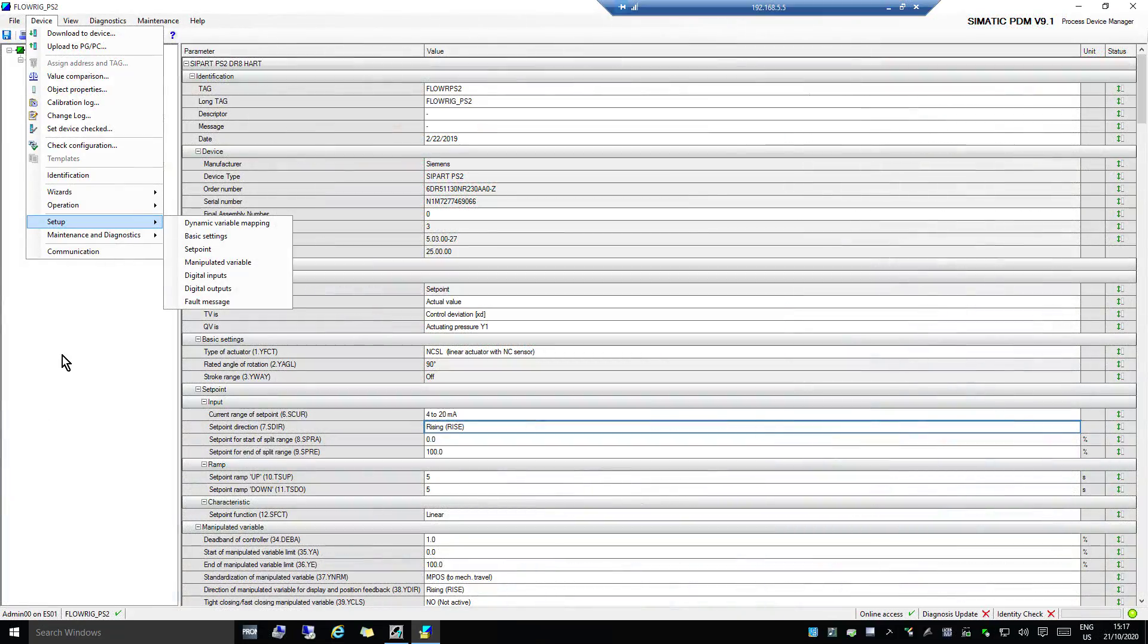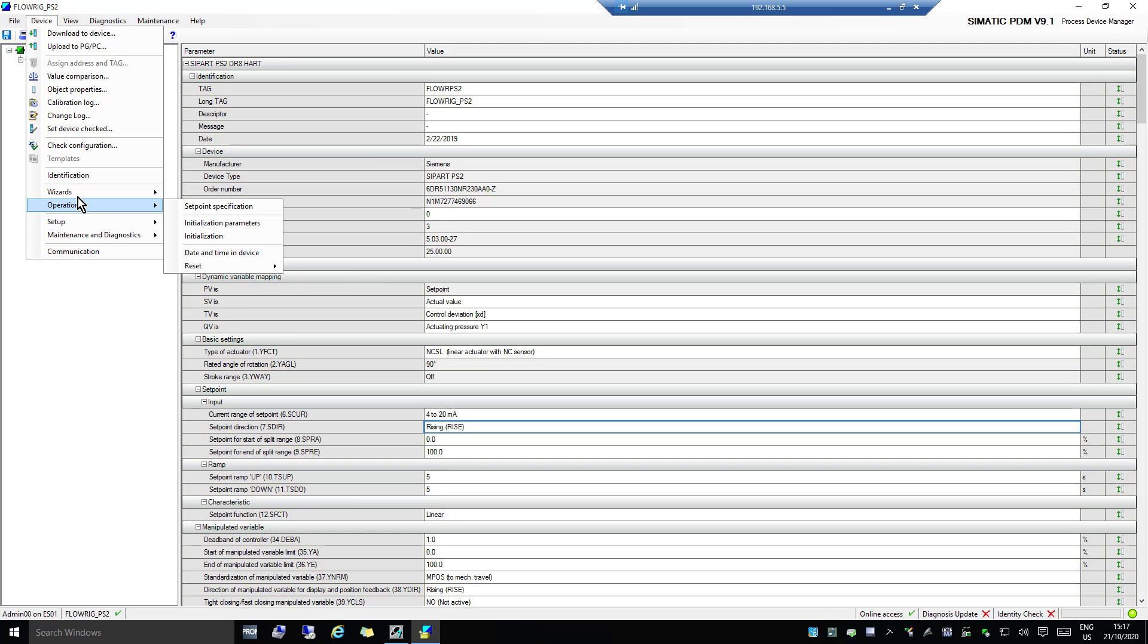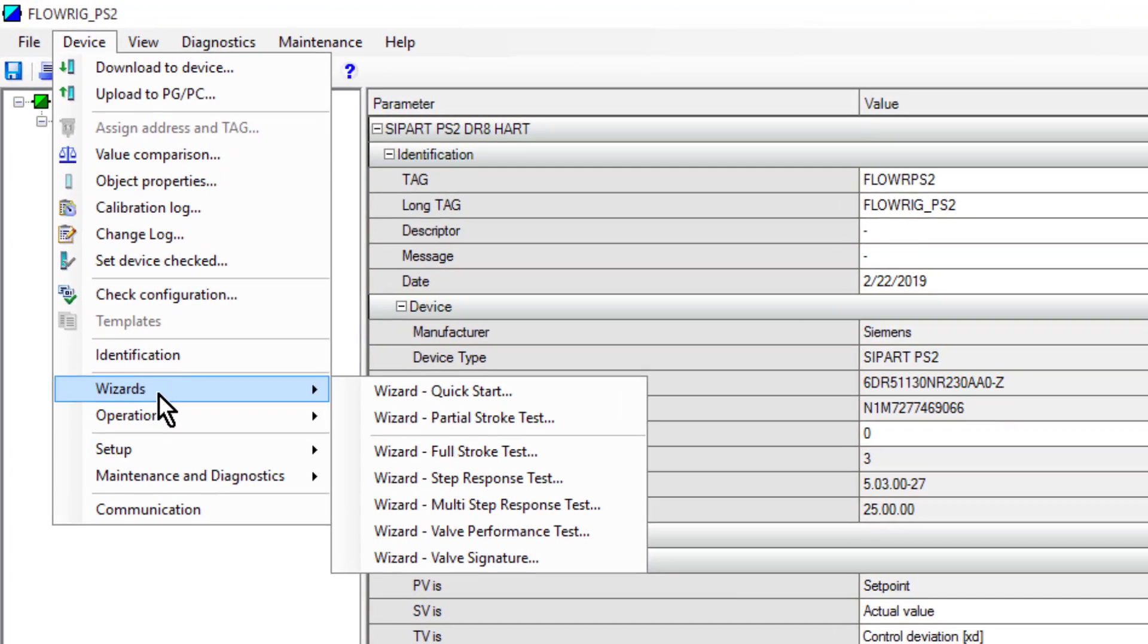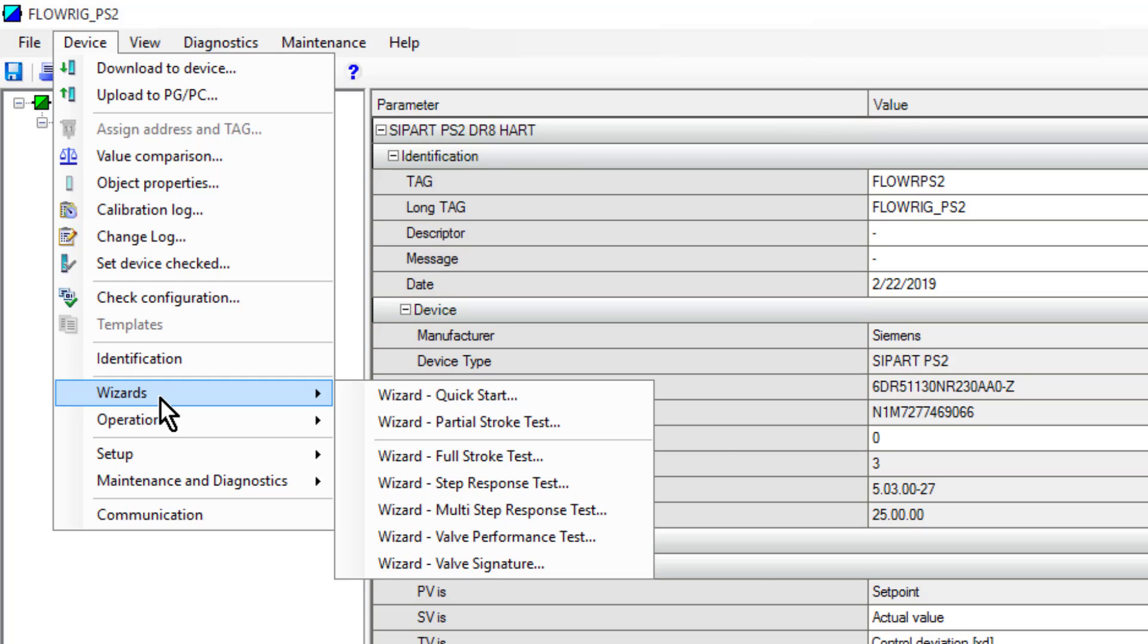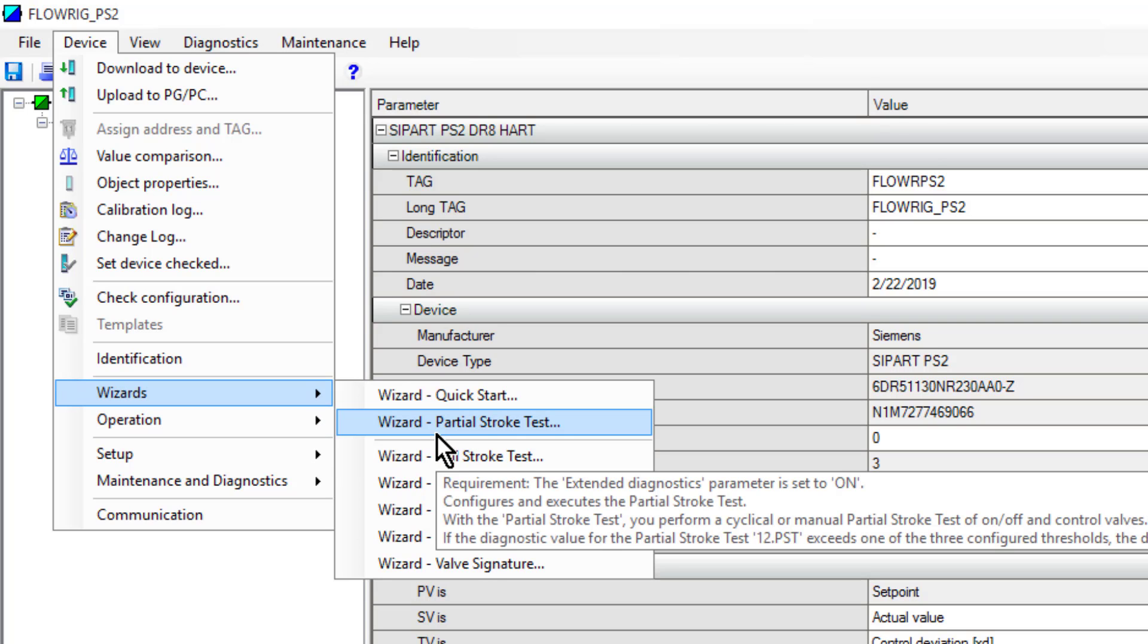We'll take a look now at the partial stroke test, which is invaluable for safety shutdown valves to make sure they are operating as they should, so when they are required to come into action, your process is nice and safe. We can see here on the wizards there is another partial stroke test wizard.